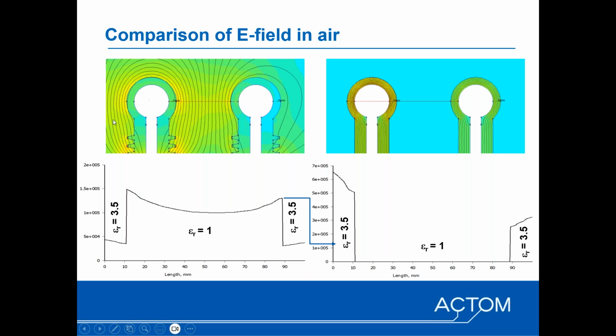Looking at the two scenarios just from a field plot and the field in the air, as I mentioned before, your high permittivity material tends to shift the field into the low permittivity material. So in this case, we do not have an earth screen. The field stress inside the epoxy is low, but the field inside the air is high. Compared to where you've got an earth screen, the field inside the epoxy might be 3 times higher, but in the air there's no field, or the air is not being stressed. And the design of the electrode and the design of the epoxy around the electrode is controlled and can be done properly, so that you can control the magnitude of the appearing field stress, so that you don't exceed the dielectric breakdown strength of the epoxy.